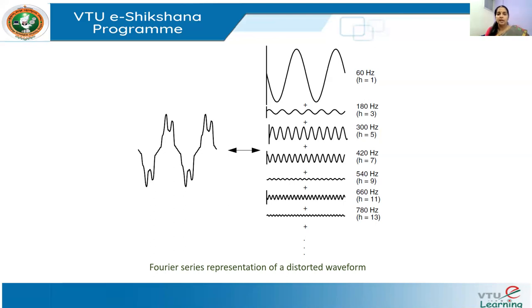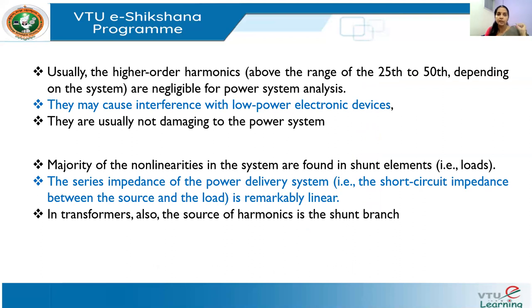As the harmonic index h increases, the amplitude of the harmonic component reduces. Higher-order harmonics, generally above the 25th, have highly negligible amplitude and do not significantly affect power system analysis. Therefore, in practice, higher-order harmonics can be eliminated from the analysis.